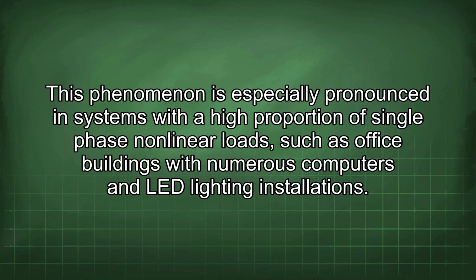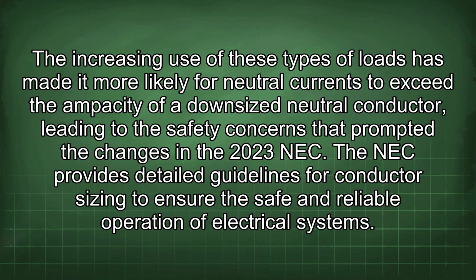This phenomenon is especially pronounced in systems with a high proportion of single-phase nonlinear loads, such as office buildings with numerous computers and LED lighting installations. The increasing use of these types of loads has made it more likely for neutral currents to exceed the ampacity of a downsized neutral conductor, leading to the safety concerns that prompted the changes in the 2023 NEC.